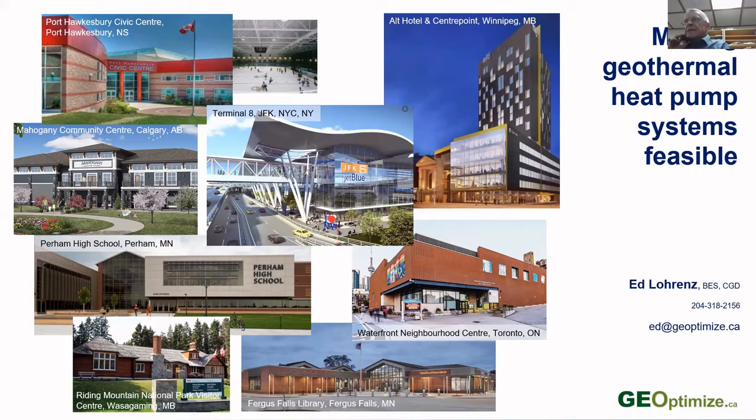Ideally, the approach that I would take on a residential building is very similar to what I would do with a commercial building. You really want to understand how much heating and cooling you need in that building, and it's going to certainly benefit you if you can reduce the heating loads at all. Because the cooling loads are so low in this province, you might consider, with the kind of glass that you're installing in the building, that it actually might be better to install the clearest glass that you can to allow the solar heat to enter the building as much as possible, which would increase your cooling requirements in the summertime, but it would offset the heating requirements in the winter, because you're dumping heat back into the ground all summertime.